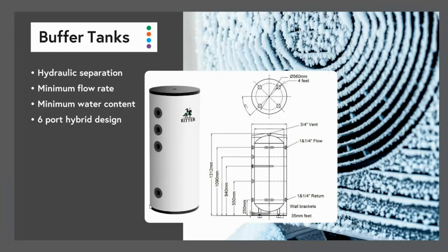What that means is on the other side, if we had radiators, for example, radiators have thermostatic valves on them. The radiators shut down and open up, and they turn on and off all the time, depending on what's required in the house in terms of comfort. That's changing the pressure and flow rate of the secondary system all the time, and heat pumps don't like that at all. So they are much better hydraulically separated with a buffer tank, so that they can see that body of water and just work against it.